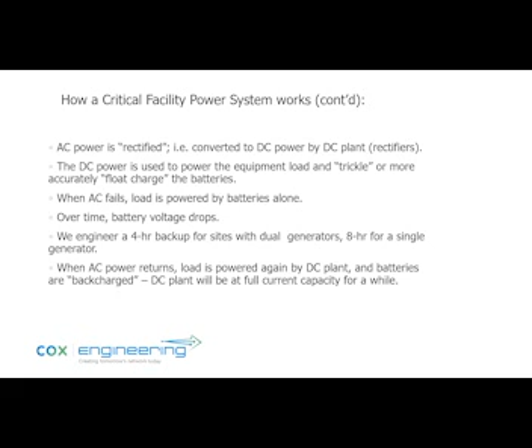We've changed that mainly because, as a lot of folks probably know, if you're on battery, your HVAC is not working. And so if you can get to even 2 hours without all of the equipment crapping out, you're lucky. So engineering for those extra hours isn't necessarily going to get you anything if the equipment temperature exceeds the threshold. Now, when the AC power returns, the load is powered again by the DC plant, and the batteries are recharged. The DC plant will be at full current capacity for a while until the battery voltage comes up. But the load out on the equipment room floor is always going to get what it wants. The batteries are just going to get whatever else is left over coming out of the plant.